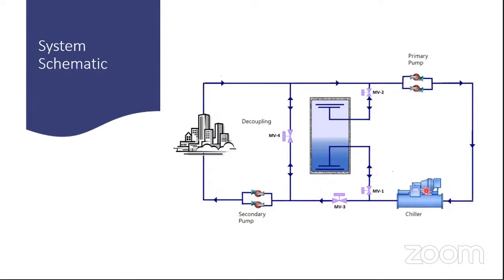And there is also a scenario when the chiller and thermal energy storage are both cooling. When the load is beyond the chiller capacity, the storage will also come into play, and the secondary pumps will operate at the desired speed, and the excess water required shall be drawn from here, from the bottom. Discharge always happens from the bottom.